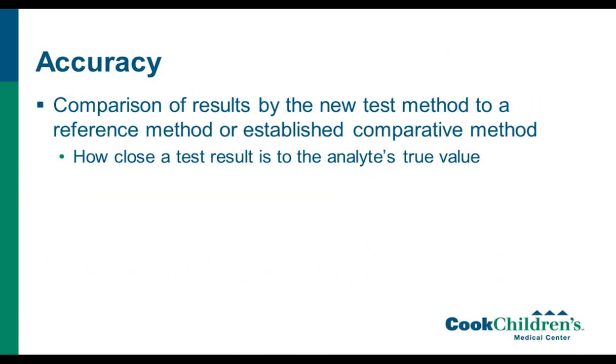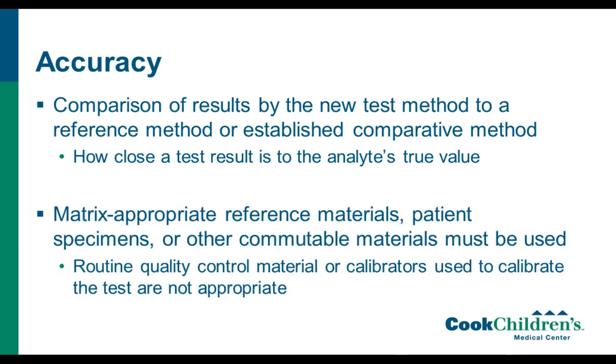When you start your validation or verification, you'll want to start with accuracy. Accuracy is a comparison of the results from your new method to the established results. You can use a reference method, but a lot of times we don't have the gold standard method available, and we're often comparing just to another established comparative method, such as an assay by another manufacturer or from another lab. You're looking at how close a test result is to the analyte's true value.